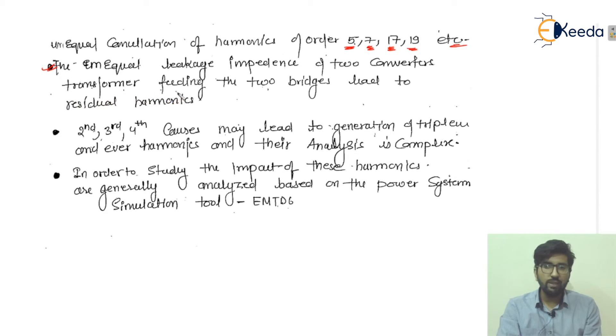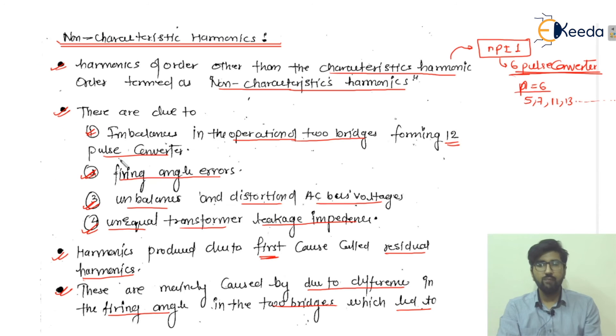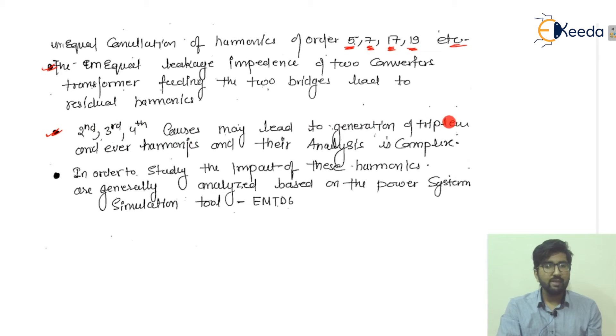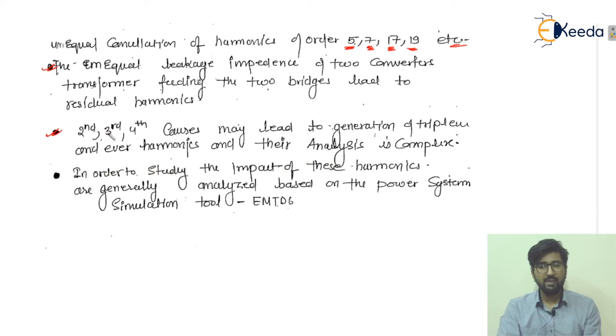The second, third, and fourth causes — firing angle error, unbalances and distortions of the AC bus voltage, and unequal transformer leakage impedance — may lead to the generation of triplen and even harmonics. The analysis of these even harmonics is complex.